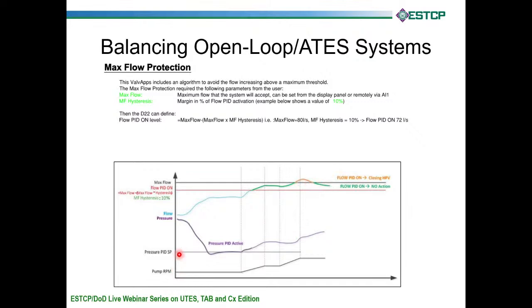Same way with the pressure set point down here. If we drop too low, then we have to close our valve down to get the pressure back up. We don't care if we're too high. That's okay. We just don't want to drop below our pressure set point. Anytime the valve closes, our pump is going to have to speed up because the pump is reacting to the needs of the building, not the needs of pressure or flow rate at the individual well, but the building overall. So our pump will react to those changes.